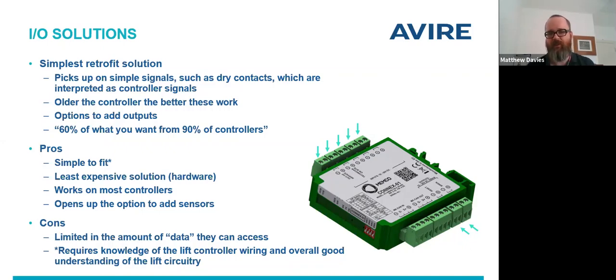I'm not looking for a specific discrete contact - give me any sort of signal and I'm happy, provided it's within those voltage ranges. The hardware is the least expensive solution available today, I'd say, in the grand scheme of things. It'll work on most controllers, and actually because of these setups, they tend to work better on the older controllers where there's more of these types of outputs available.